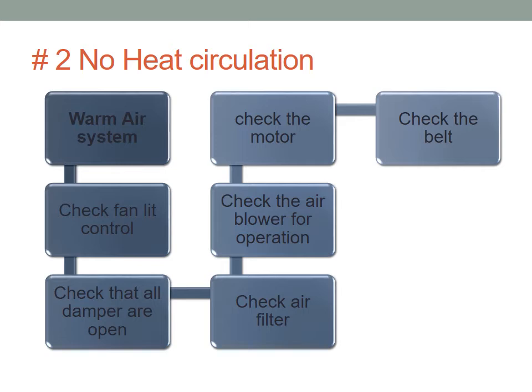No heat circulation, and this time it's a warm air system. So check the fan is on. Fan limit, this is the fan limit control. Check that all the dampers are open. If the damper is closed, there is no airflow. That's kind of like the valve in a water system.